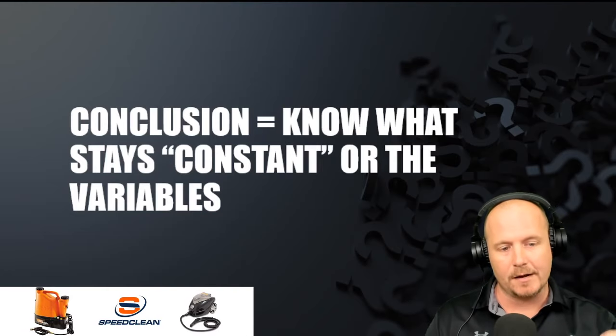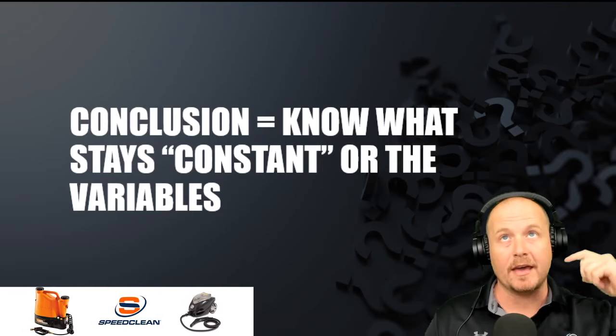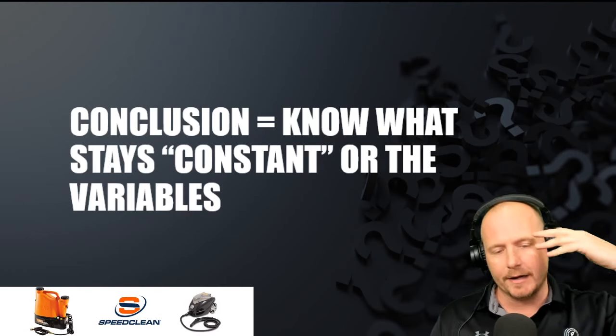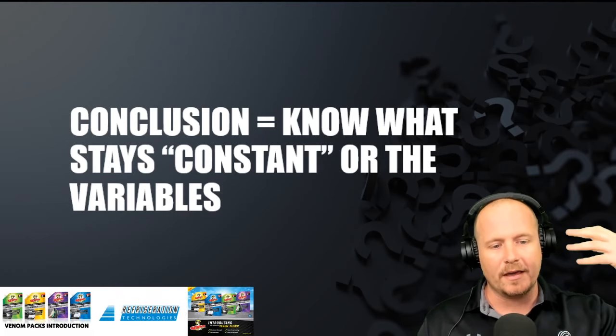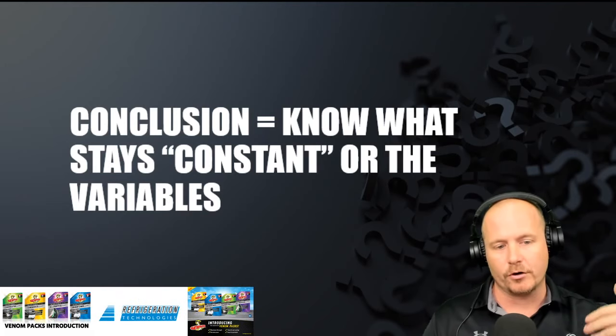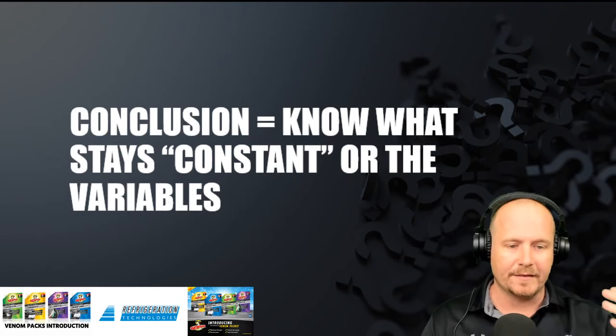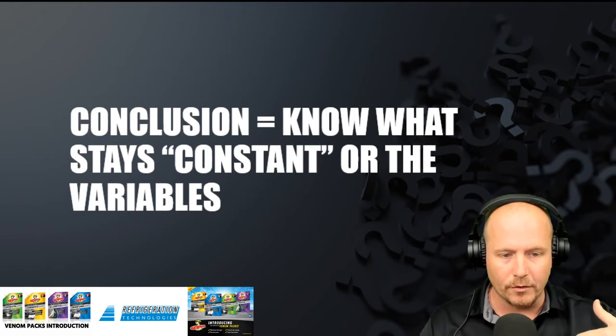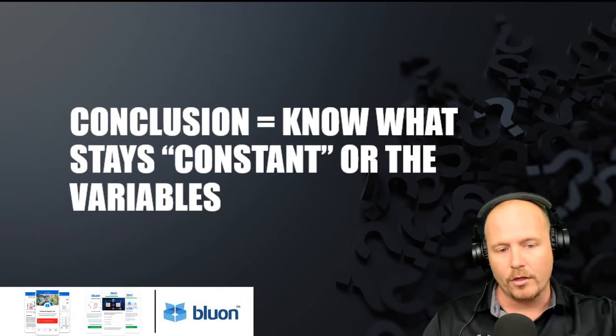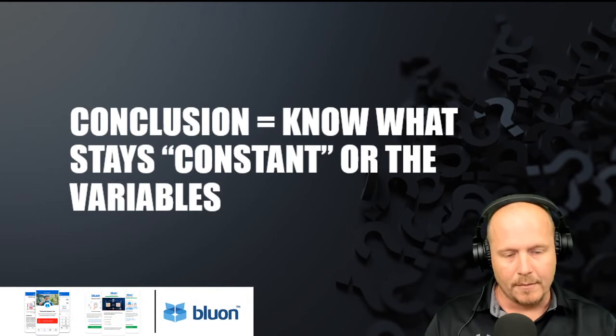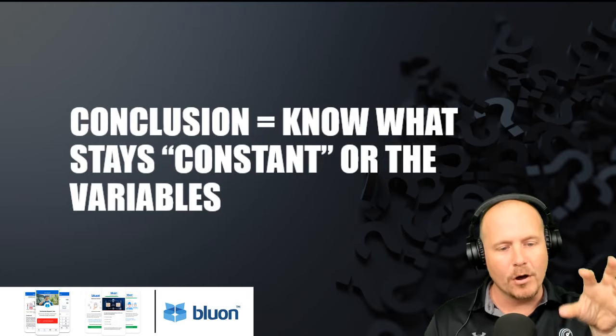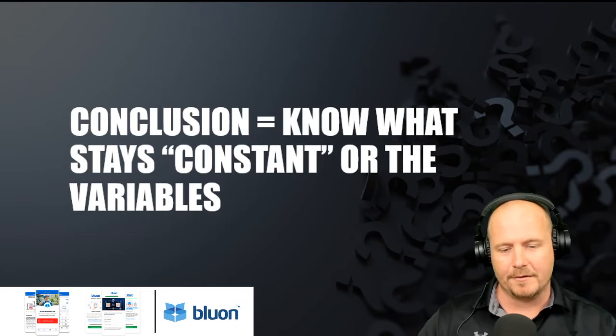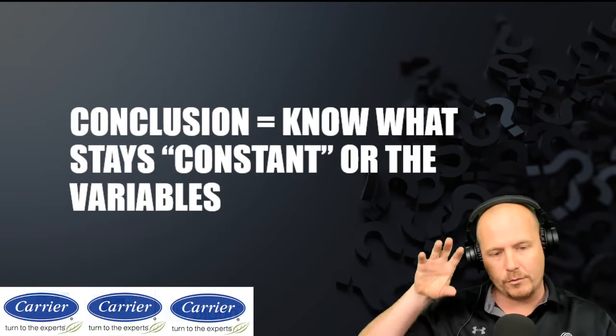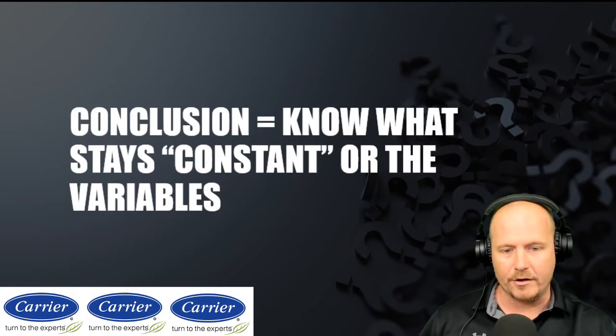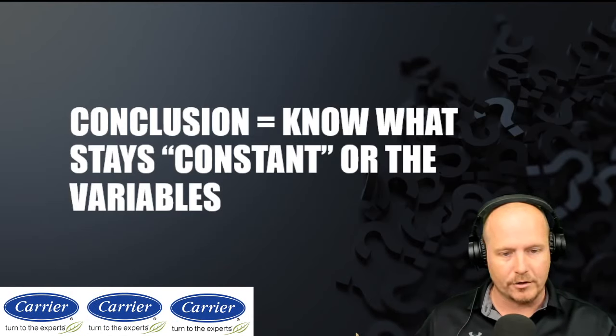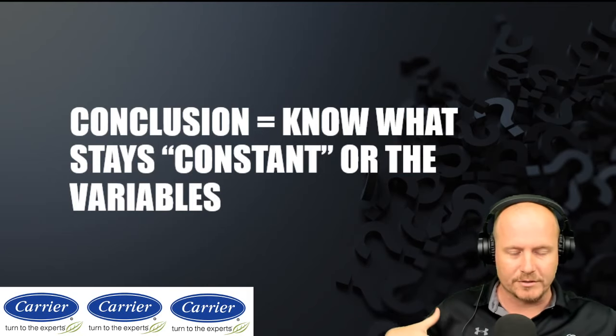I'll end here because this is a common mistake people make, thinking that when you decrease your voltage, your current goes up. The reason they think that is because they've seen things like a 120 volt motor drawing double the current of a 240 volt motor. Say it's a 3/4 horsepower motor, and you have them sitting next to each other, one's 240, one is 120, and the 120 draws double the current, so you just assume lower voltage equals higher amperage.